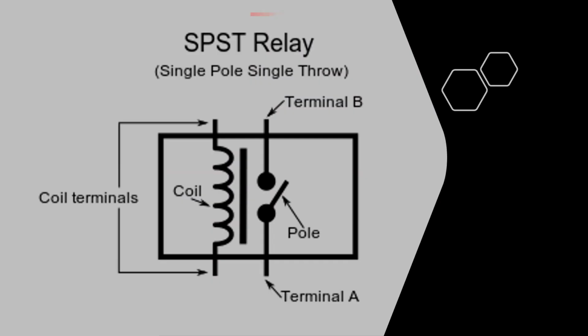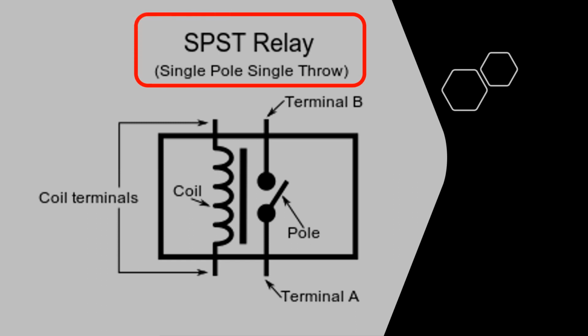This is an electrical diagram of a single pole, single throw isolation relay. It has, of course, the coil, which is normally 24 volts, but it also can be a high voltage coil if needed for your application. It has a set of contacts which are normally open, and when the coil is energized, this contact closes, allowing voltage to flow to the circuit that is connected to this relay. This is the most common type relay that is used for isolation.